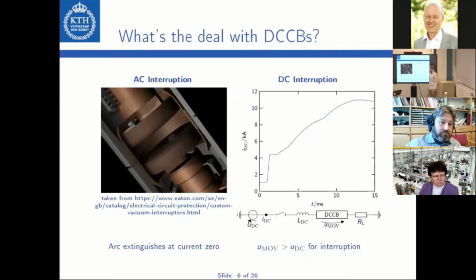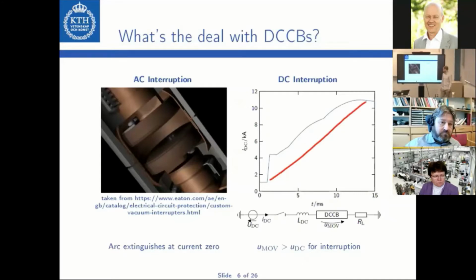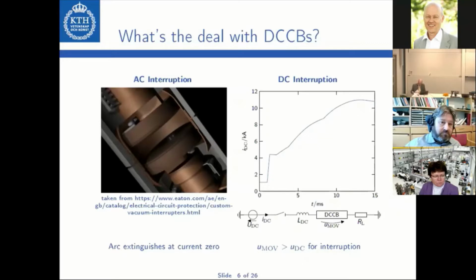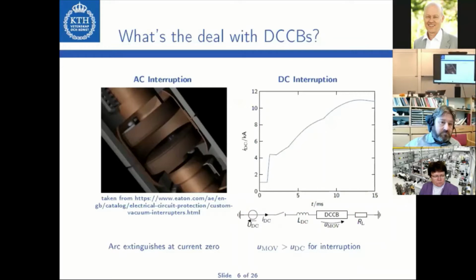In the DC system, however, the fault current never crosses zero naturally. Here you can see an exemplary fault current for a DC system. As you can see, the current more or less increases up to some steady state value. If one would apply the AC circuit breaker on the DC side to handle such faults, the arc would never extinguish because of the lack of the current zero crossing. Therefore, specialized DC circuit breakers have to be used. Down here you can see a simple DC circuit consisting of a DC source and a DC circuit breaker. In order to interrupt the current flow, the DC circuit breaker must insert a counter voltage that exceeds the DC source voltage. Two practical implementations are possible.